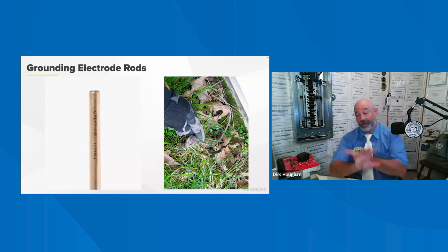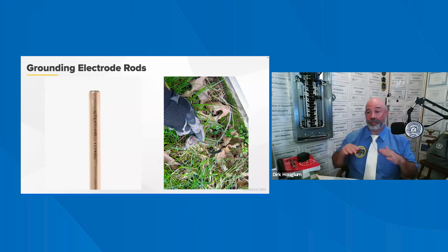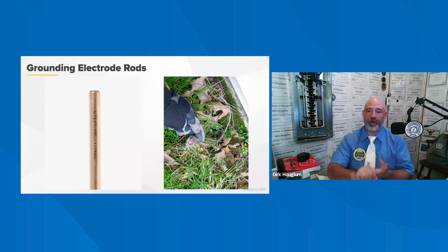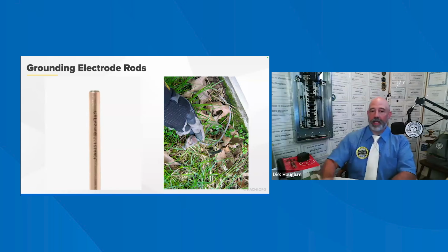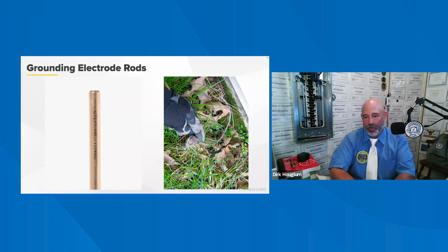and ground. Sometimes, in very rocky earth, they can be driven at an angle no more than a 45-degree angle. Now, they can be installed in a trench no less than 30 inches deep, but no part of any grounding electrode can be closer than 6 feet to another one. The upper end of the electrode should be flush with the ground, or at least below the ground surface, so that the end and the attachment are protected from damage. If you find a rod sticking up out of the ground, that's a defect. It should be at or just below soil surface.